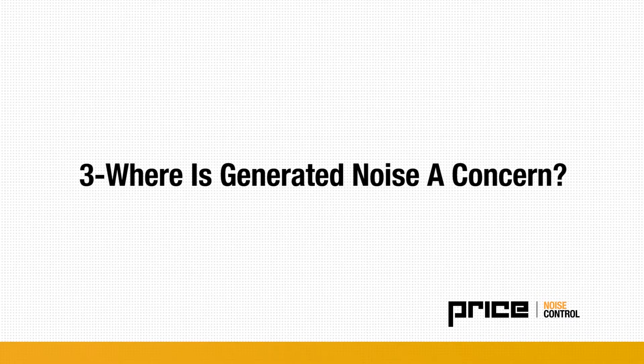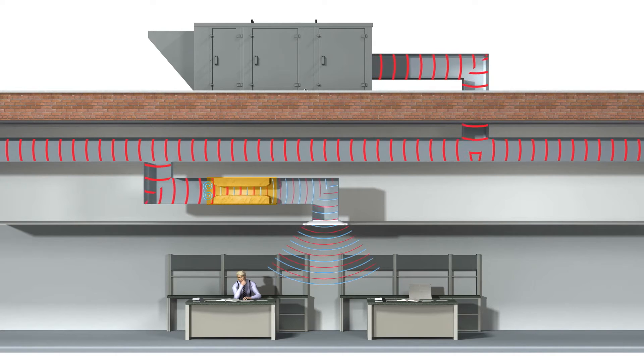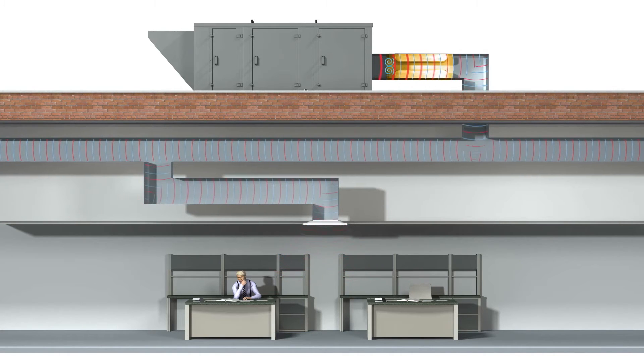So when is silencer generated noise a concern? Typically, generated noise is only an issue when the duct elements are in close proximity to occupants. Silencers should be positioned as close to the noise source as possible, which typically eliminates their generated noise impact on receiver spaces. Let's look at two examples to better understand how silencer generated noise contributes to overall noise levels.